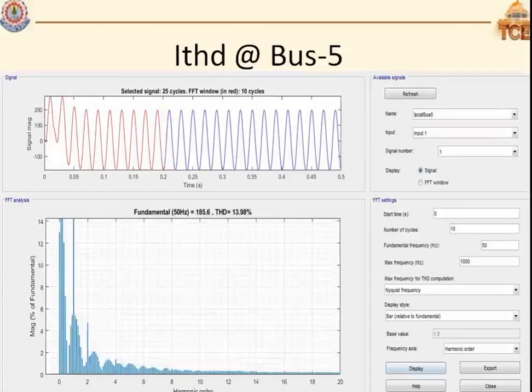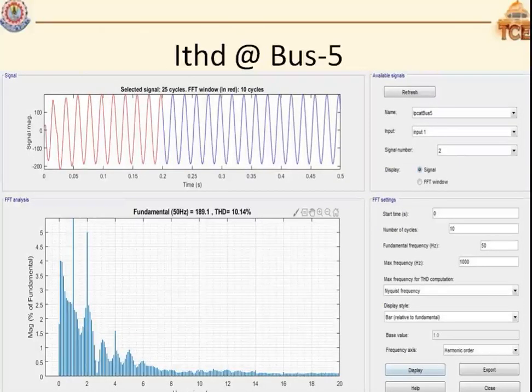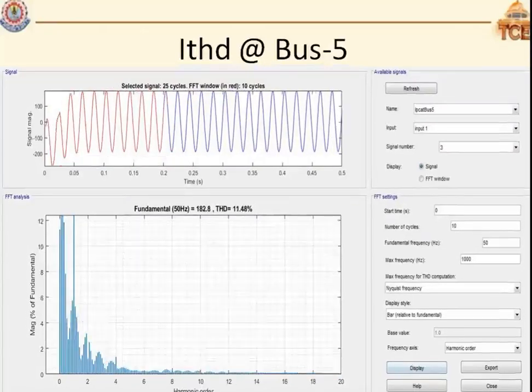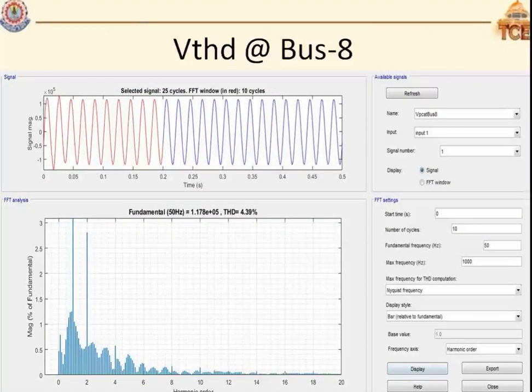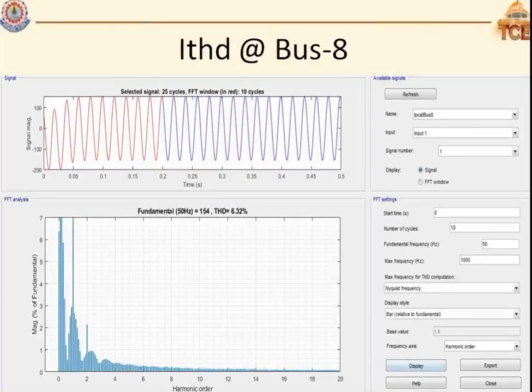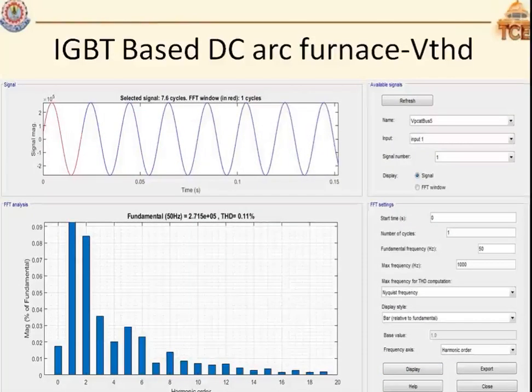When we compare to the AC arc furnace, we can't predict the nature of harmonics, so we can easily go for a DC arc furnace. And also for a DC arc furnace, the electrode consumption is low, because in a DC arc furnace there will be only one electrode. For an AC arc furnace, for 3 phase we have to install 3 electrodes. And here are the voltage THD at bus 8 and current THD at bus 8 for the 12 pulse thyristor based configuration.